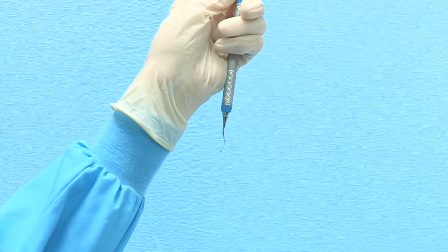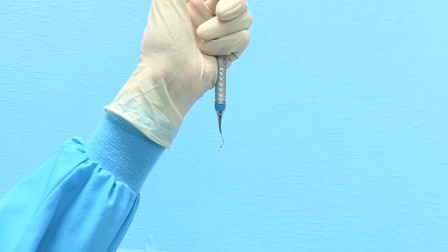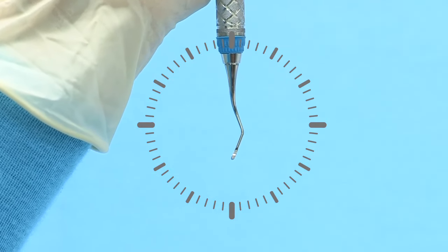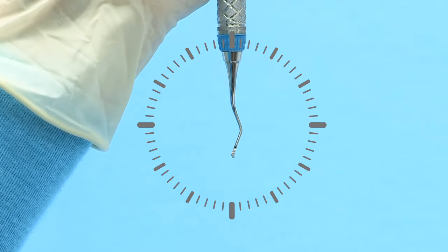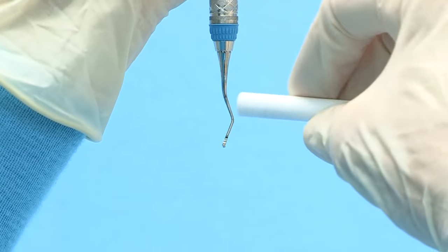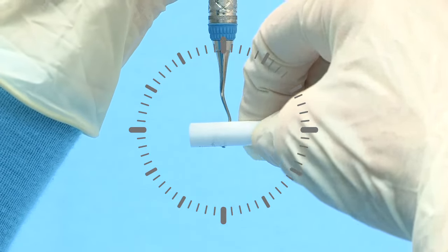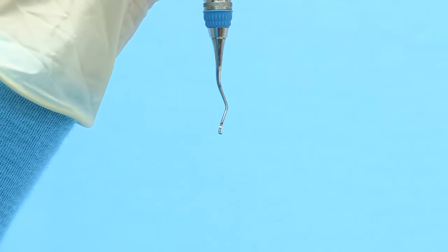To finish the facial surface of an even-numbered Gracey Curette, hold the terminal shank at three minutes after 12 o'clock with the toe pointed toward you. Position the cylindrical stone along the face of the blade horizontally at three and nine o'clock. Lightly roll the stone along the face of the blade from heel to toe.